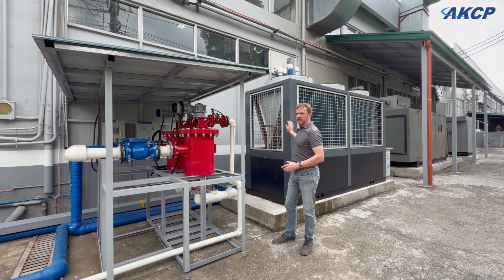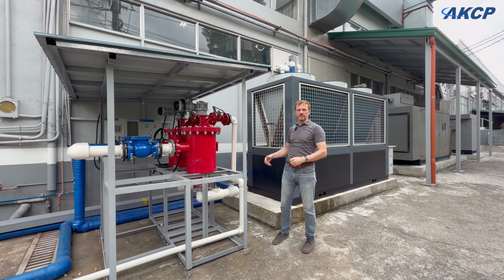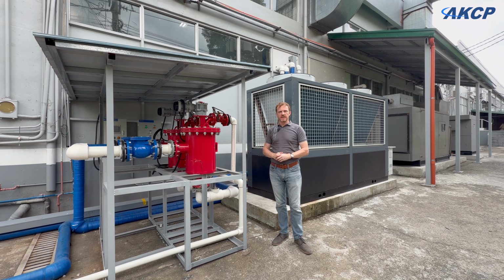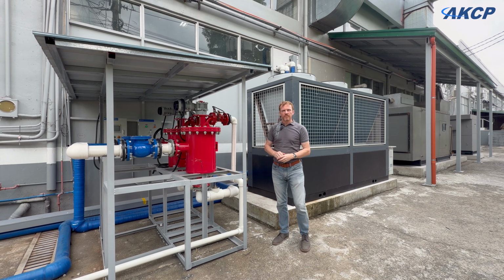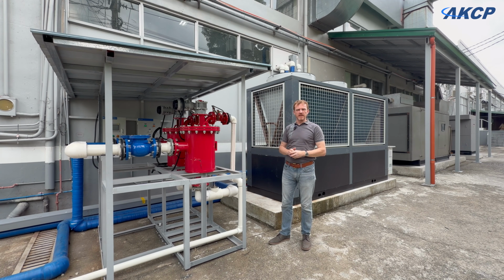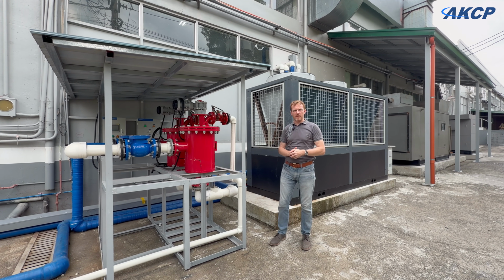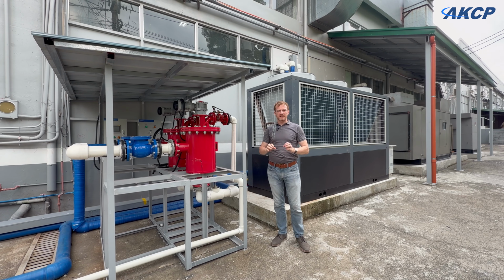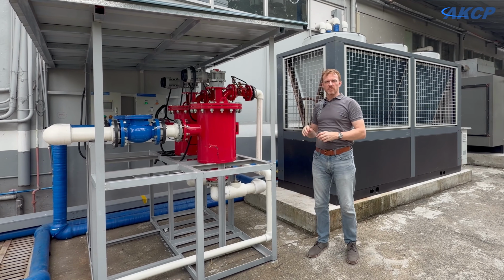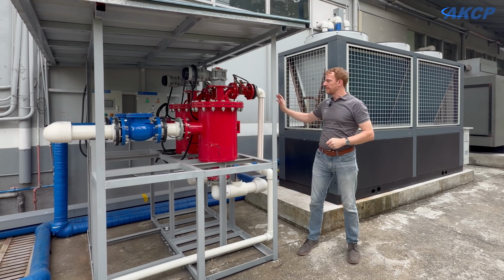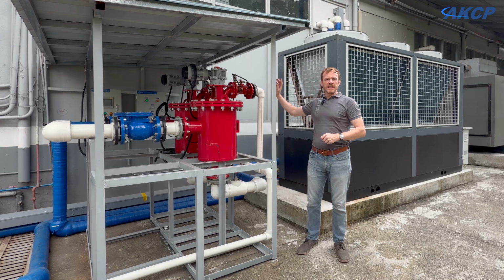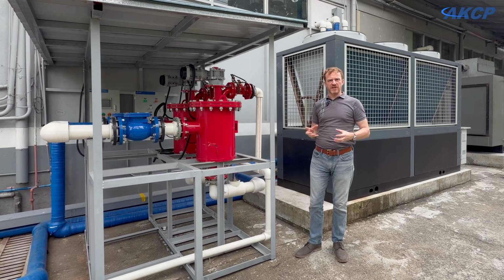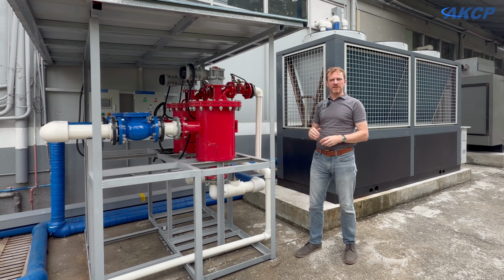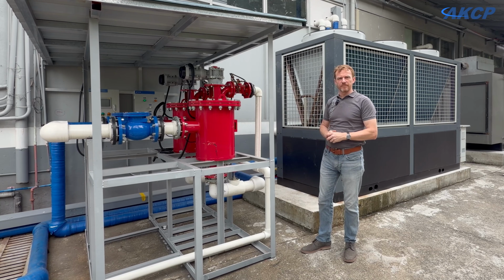So this chiller is going to generate the cold water we're going to send back to the data center to use in the cooling loop. It is a closed loop system, meaning we have no adiabatic or evaporative cooling going on, so it's zero water usage. The water is simply circulated from here through these filters into the heat exchangers through a pressure tank, which provides us hydraulic separation before it comes back to here.